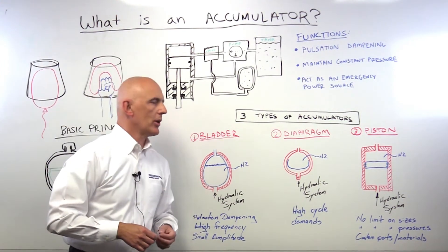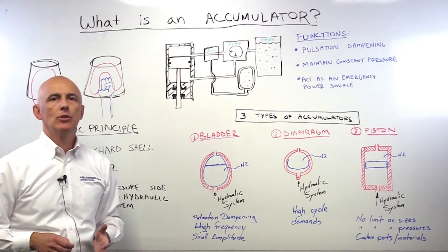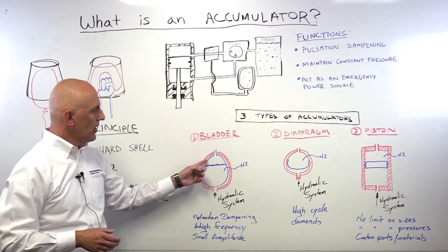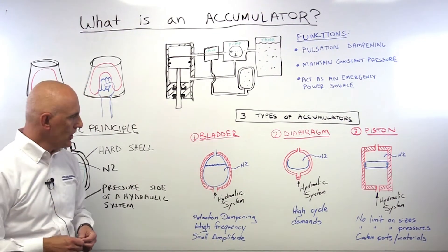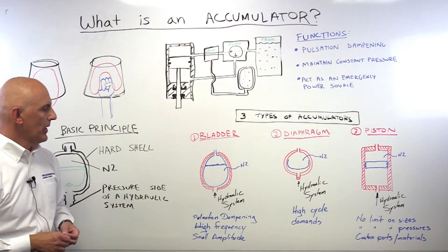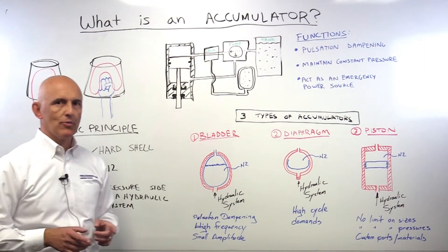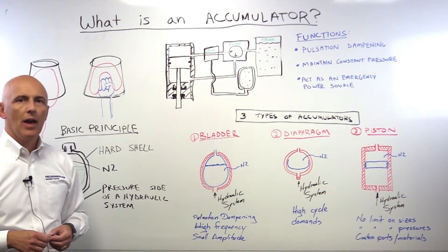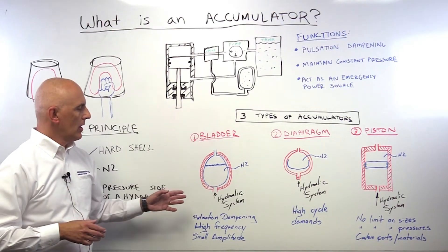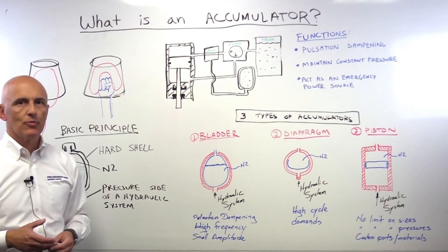Here we come to the three different types of accumulators: the bladder, diaphragm, and piston type. Bladder is the bread and butter — you can use bladder accumulators everywhere, and most hydraulic systems use them. Basically, you have a bladder bag with a pre-charge of nitrogen connected to the hydraulic system. These accumulators are used in pulsation dampening, especially where you have high frequency and small amplitude. However, this type has a restriction: the bladder has a vulcanization seam, and this is the weak point. If you have high frequency in a high cycle demand, you can have a rupture in this seam.